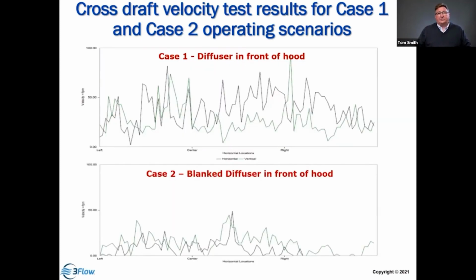Now, we also want to look at this magnitude of variation. We are taking readings out of the traverse, which allows us to take 30 readings at each location. And when we look, you can see the range of turbulence. So this is air impact on the opening. And the hood is trying to overcome that turbulence and maintain containment.